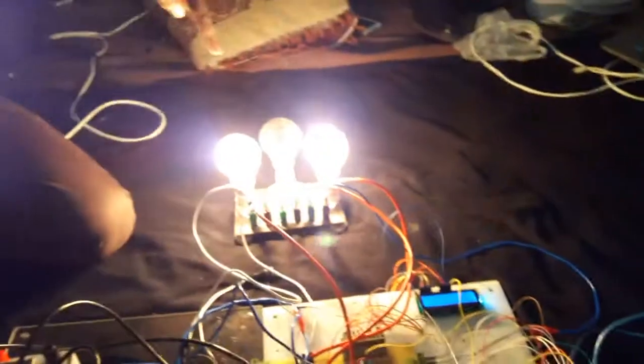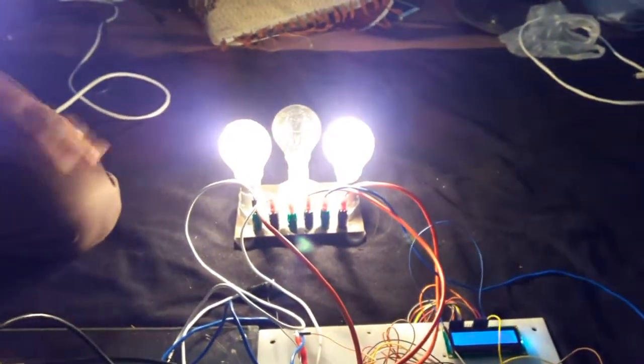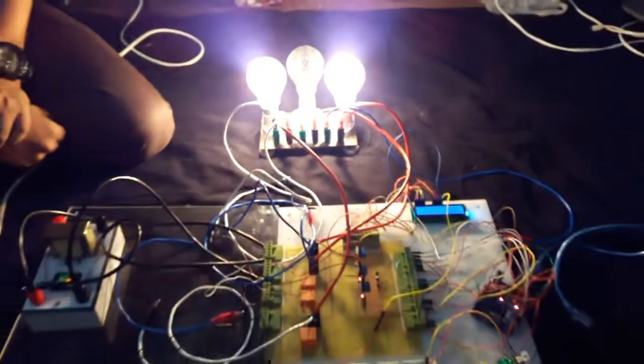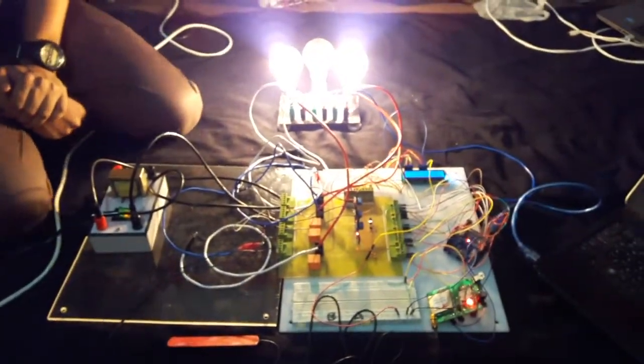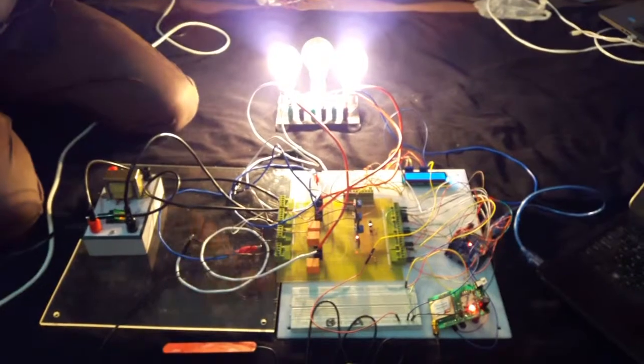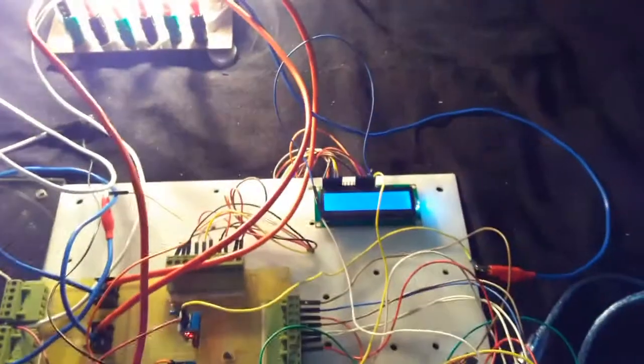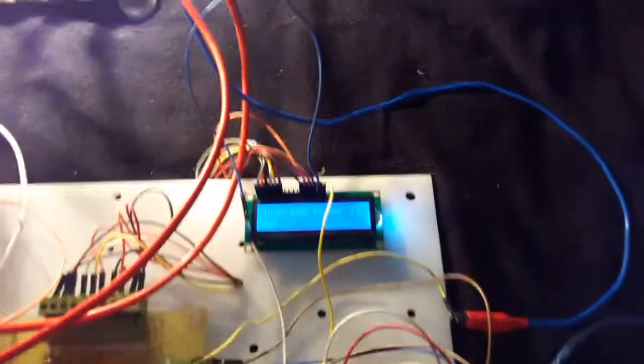This is a GSM SIM 900 that we are using, and we have set the trip power to be 80 watts, which when consumed will give 2 warnings to the user. After the 2 warnings that are shown in the serial monitor, the greatest of the loads, which is the 40 watt, is shut, and after a fixed time it will be turned on, which will be the rehabilitation of the load, as is the concept of partial shedding of loads. Constantly the power consumed will be given by the display, as it will be shown here.